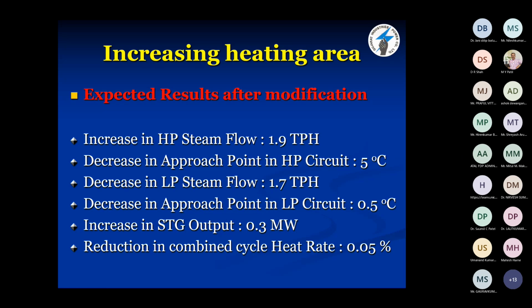So the flue gas temperature in the LP section will be low. The steam flow of the LP section has reduced. Decrease in approach point in LP circuit, 0.5. An increase in STG output, that is steam turbine output, by 0.3 megawatt. And the reduction in combined cycle heat rate, that was 0.05%.